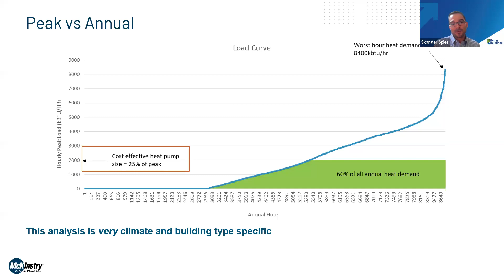What we're talking about is a composite heat pump plant, where we use a perhaps relatively expensive but very energy efficient heat pump to do most of our heating most of the time. Then we use low cost and inefficient traditional equipment like boilers and furnaces to meet those occasional really high peak demand loads. That gives us an optimized heat pump plant that has a much smaller carbon footprint, uses way less primary energy, and can be a very effective system for your building overall.